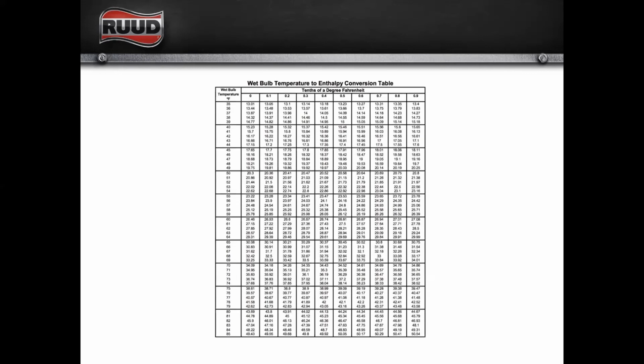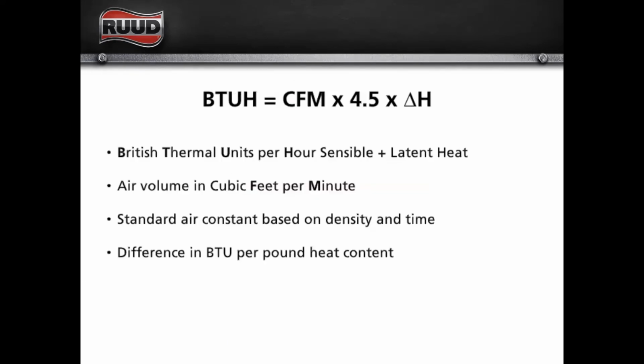And what enthalpy is, enthalpy is the amount of BTUs in a pound of air. Now, a pound of air is going to be a different volume of air depending on the temperature, but it just tells us how many BTUs per pound of air, and that's what enthalpy is. And so we have to take wet bulb temperature, convert wet bulb to enthalpy, and plug those numbers into our formula. Right. So here's our formula.